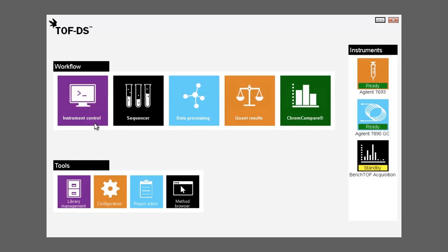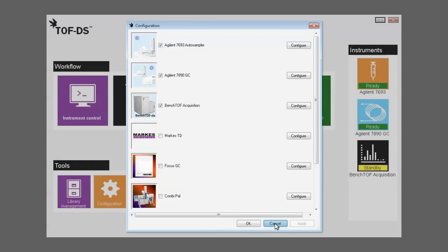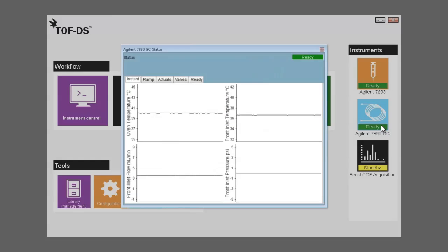Like BenchTOF, TOF-DS is platform neutral, which means that users can configure their preferred autosampler and GC, minimizing any training requirements or the use of multiple software platforms. The required components are simply selected from the list, and then they appear in the Configured Instruments panel on the right-hand side.